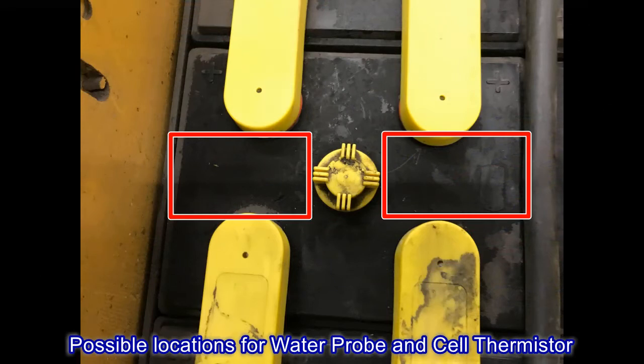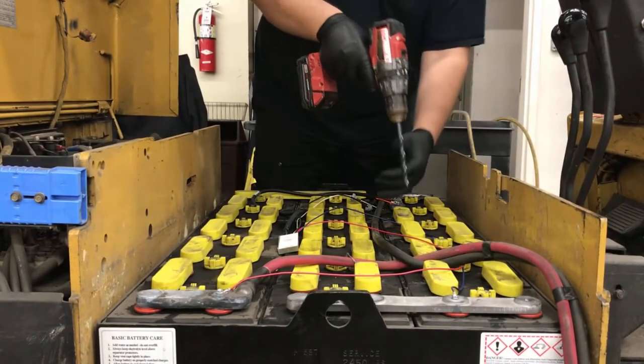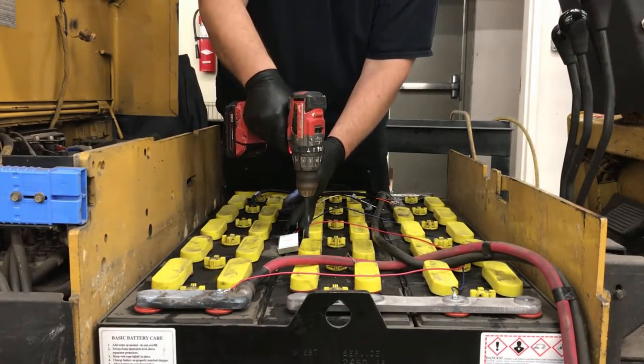Locate spots on the battery for the water probe and cell thermistor away from battery posts. The water probe and thermistor should be in different cells near the center of the battery, and the water probe should be at least 4 cells from battery negative. Carefully drill a 1/2 inch pilot hole through the top of one cell for the thermistor and in a different cell for the water probe.